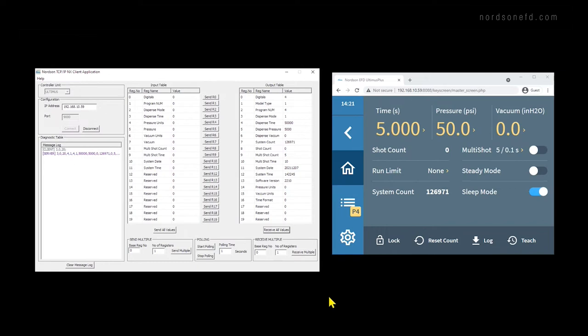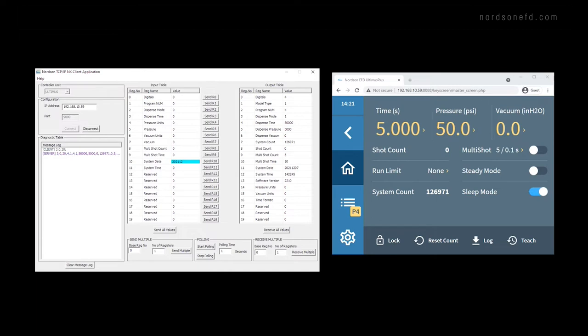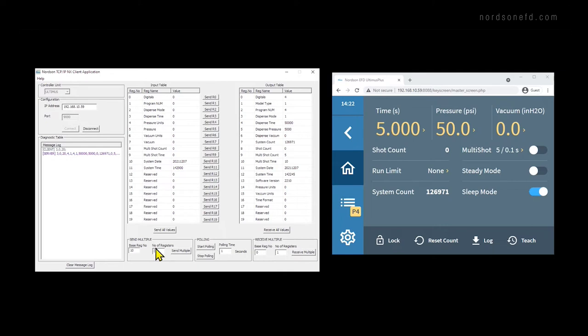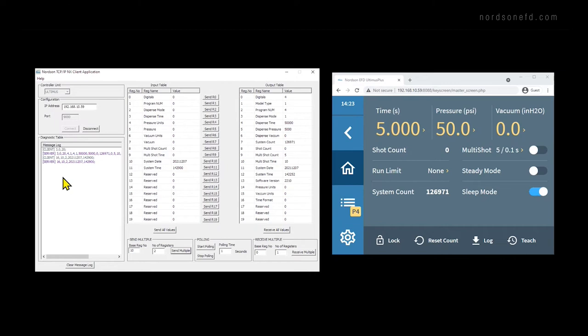So let's put the correct system date and time in. For the system date, the year 2021, followed by the month, 12, followed by the day, which is 7. But we need to put in two digits, so it's 07. Then the system time, it's now 2:29 p.m. So in military time, that's 14, 29, and then I'll add two zeros for the second. To send both of these values, I can use the send multiple area down below. For the base register number, I'll use 10, since that's the first register. And the number of registers I want to send is 2. Then I can click the send multiple command, and it will send those values.